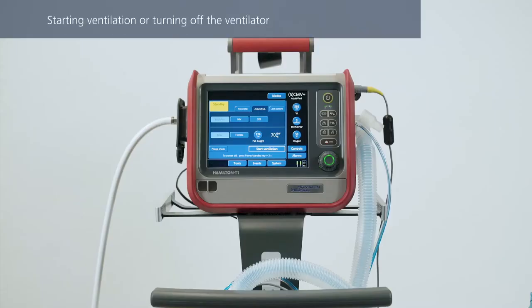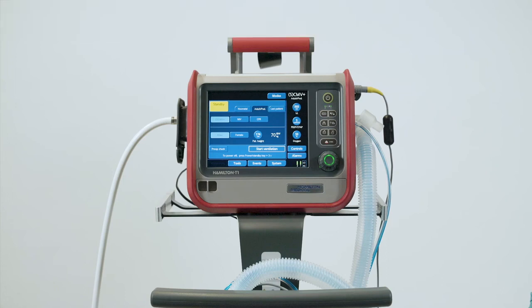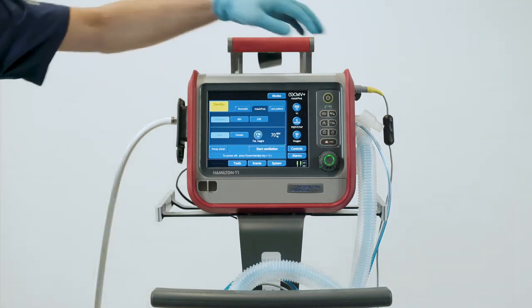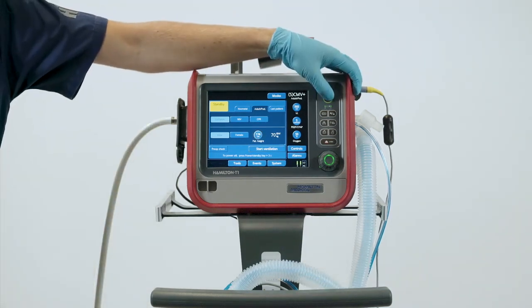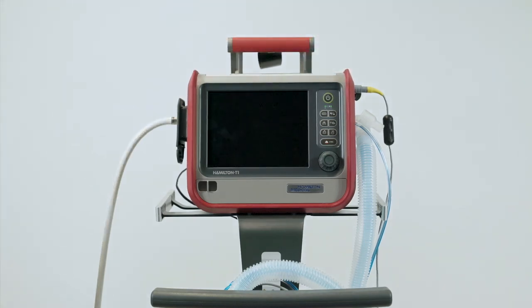Once you've finished the pre-op checks, the ventilator is ready to use. You can set up the ventilator for a particular patient and start ventilation. Or you can turn off the ventilator and keep it stored away, ready for use. All the test results of the pre-operational checks will remain stored in the memory, even when the ventilator is turned off. But make sure that the setup you calibrated is not changed or altered while the ventilator is in storage. To turn off the ventilator, press and hold the power standby key for about 3 seconds.